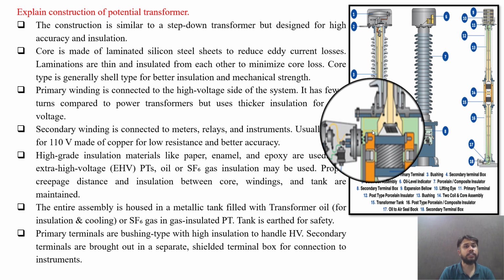Explain construction of potential transformer. So generally this potential transformer is known as the PT. These PTs are used as a voltage input to the relay on the secondary side. So the construction is similar to a step down transformer but designed for high accuracy and insulation.